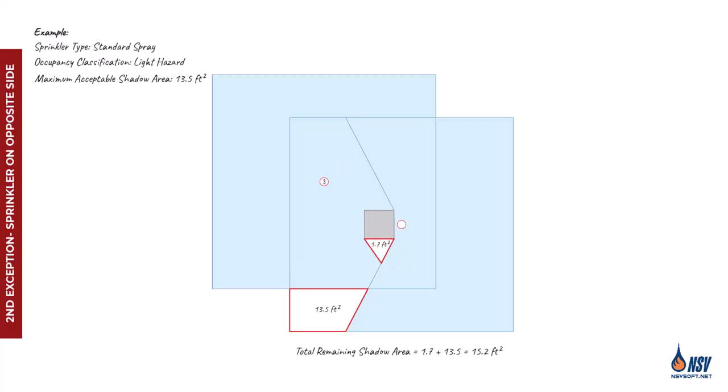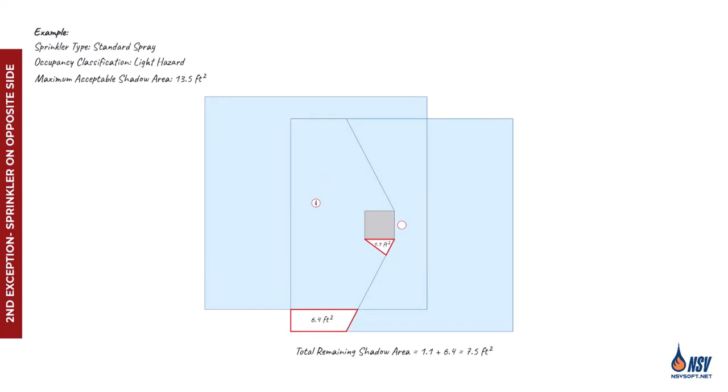Sprinkler 3 covers more of the shadow area than sprinkler 2, but the remaining shadow still exceeds the acceptable limit. With sprinkler 4, the remaining shadow area drops to just 7.5 square feet, which is below the threshold, so sprinkler 4 can be considered the opposite side sprinkler for the first sprinkler.